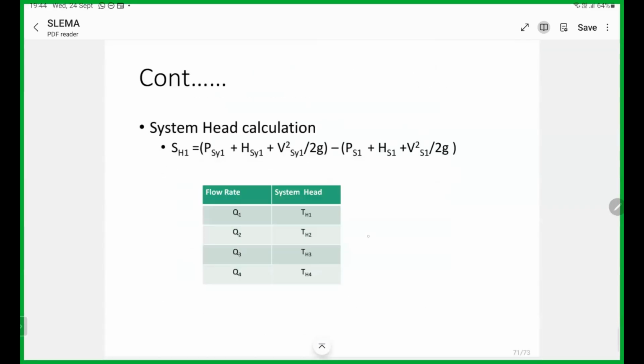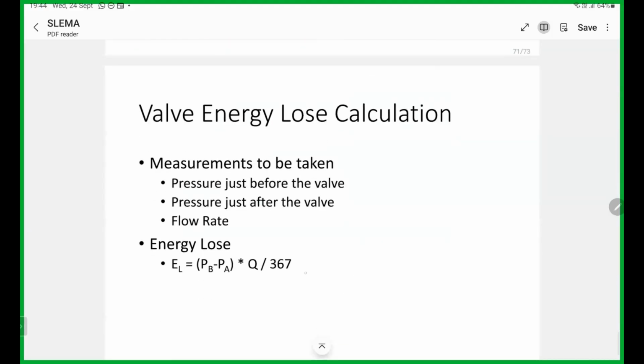Then we can draw the system curves practically. Then the energy loss calculation for valve throttling: we can measure the pressure before and after the valve, with the flow rate somewhere here. Measure PB and PA; PB minus PA is the pressure loss in the valve. Multiplied by the flow rate divided by 367, you can calculate the valve loss using this equation. Then you can quantify how much we can save by removing that valve throttling. Ideally, introduce a VFD, then you can calculate the energy saving and the payback period for this.